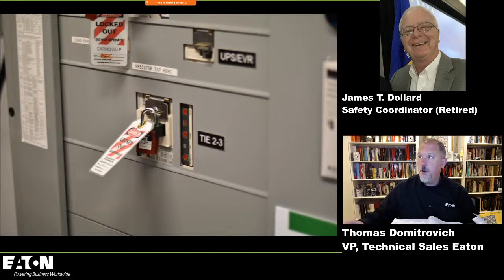Very good point. And then there's just an example of where, when those provisions are there for a lock, that's there to receive the lockout tagout, and then I could lock that breaker and still take that panel off if I had to. And that's a good picture because that lock would be acceptable in a lockout tagout procedure because it's identified as a lockout tagout lock. It's not the same lock that you're going to use on a Knox box or on a door, and you've got a tag, and the other side of that tag should have the name and contact information of the individual that applied the lock. Ah, okay.